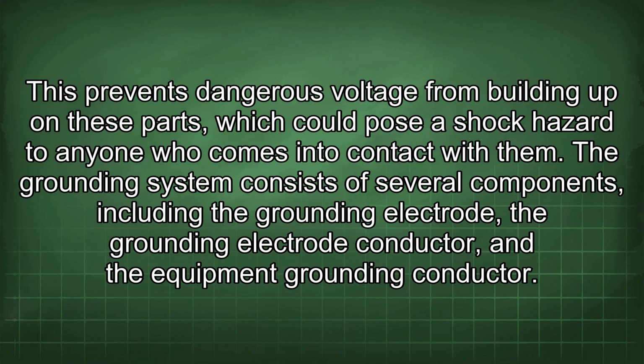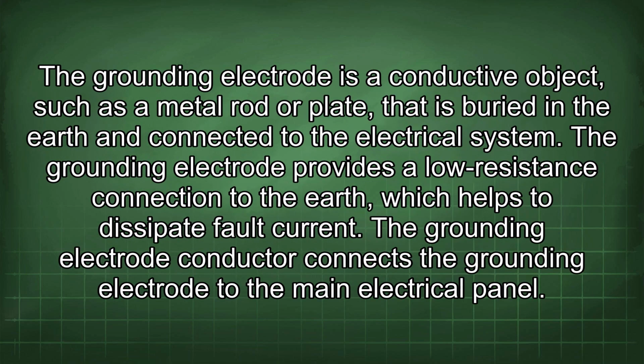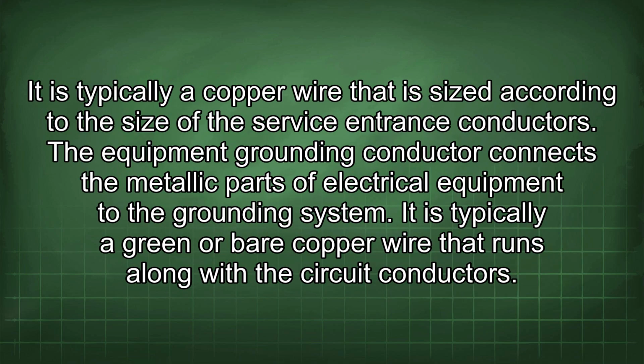The grounding system consists of several components, including the grounding electrode, the grounding electrode conductor, and the equipment grounding conductor. The grounding electrode is a conductive object, such as a metal rod or plate, that is buried in the earth and connected to the electrical system. The grounding electrode provides a low resistance connection to the earth, which helps to dissipate fault current. The grounding electrode conductor connects the grounding electrode to the main electrical panel. It is typically a copper wire that is sized according to the size of the service entrance conductors.